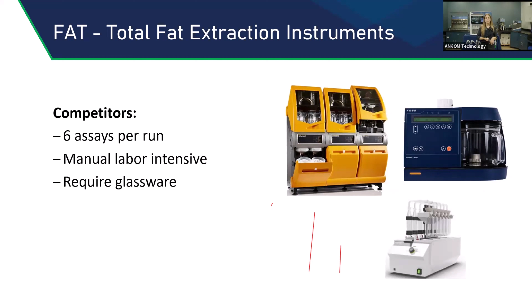Our direct competitor to the instruments you saw on that screen is our HCl hydrolysis system. So this system uses our filter bag technology, eliminating the glassware. You can do sample sizes from 1 to 2 grams, analyze oil from 0 to 100%. Again, it's 15 samples at a time in this run. You would go straight from this into our extractor.